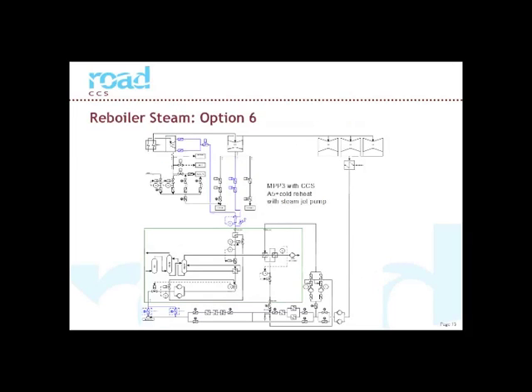Now we zoom into the process flow diagram of this steam solution. On top you see the steam turbine of the power plant. From left to right, a high pressure steam turbine, the medium pressure steam turbine, and the 3 low pressure steam turbines. At full load of MPP3, the steam is extracted, leaving the medium pressure steam turbine. In part loads, the pressure is not high enough for the capture plant. The capture plant is presented in the green box.